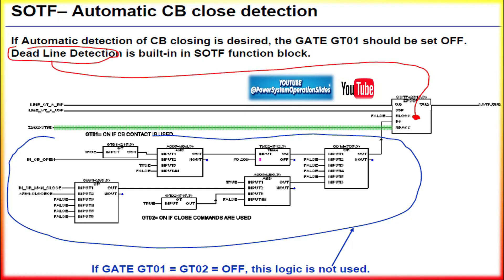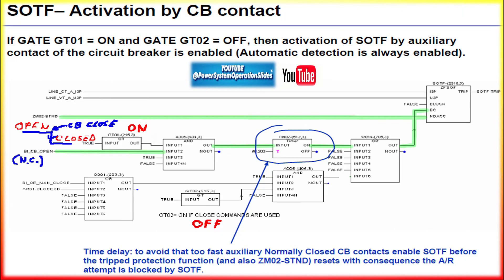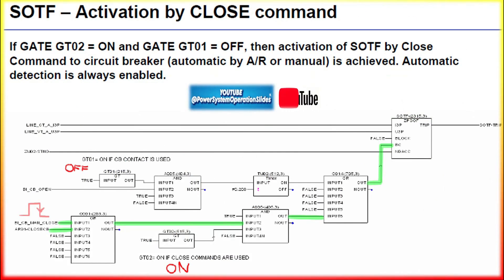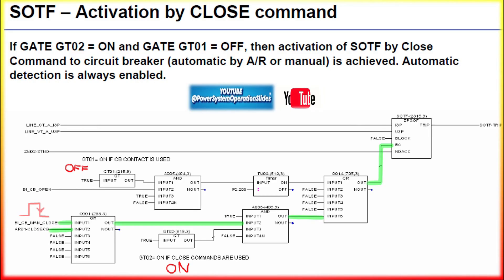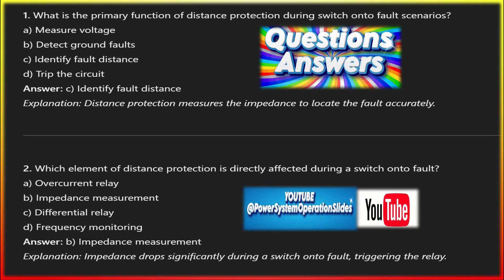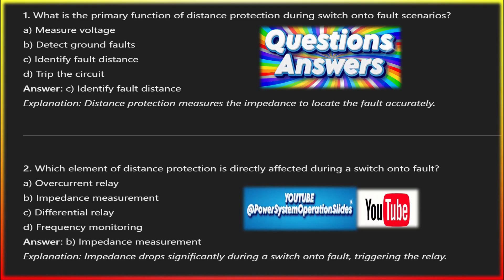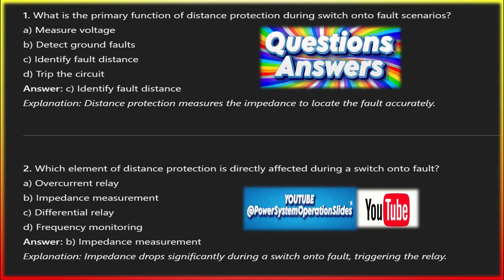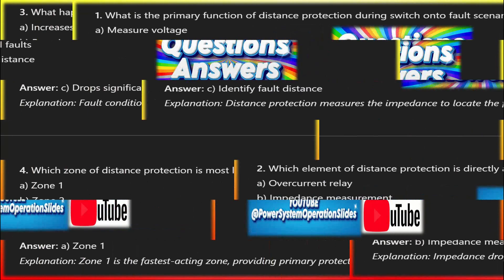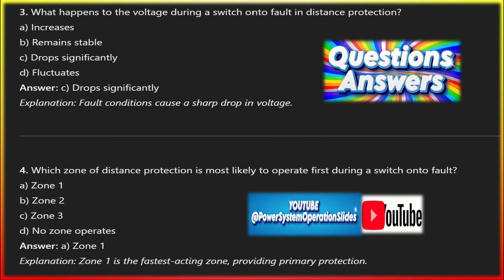In traditional distance protection schemes using impedance zones, the relay measures the impedance of the transmission line between itself and the fault. Different zones of protection — Zone 1, Zone 2, Zone 3 — correspond to various portions of the line. For instance, Zone 1 is typically instantaneous and protects a certain percentage of the line, typically 80 to 90 percent, while Zone 2 protects the remainder of the line with some time delay. Zone 2 and Zone 3 typically have a time delay to ensure selectivity so the nearest breaker operates first and distant breakers only operate if the fault persists. However, with SOTF, the delay mechanisms are bypassed to provide instantaneous tripping, ensuring that the fault is cleared without waiting for the impedance zones to determine the fault location.